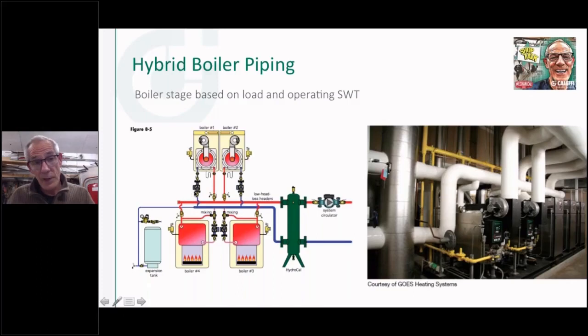So the same thing could be going on here. I could have different size boilers. I could have different size pumps. You can see that we put return temperature protection by putting a thermostatic mixing valve on these cast iron boilers. So if they do get a slug of cold water, that valve is going to assure that we don't thermally shock those boilers. And again, there's our point of no pressure change being established through this header.